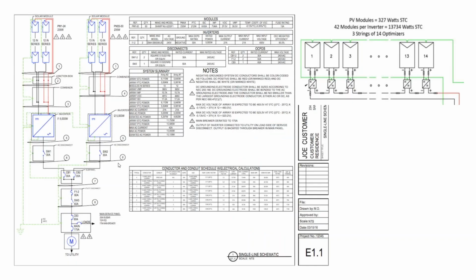So the question becomes: how do you determine the right setup? With Enphase microinverters, we know up to 16 per branch circuit. Microinverters are very flexible—if you just wanted a one-panel solar array, a microinverter would work just fine. String inverters, on the other hand, require you to know how many modules you can wire into a circuit so you don't overload the string inverter, which relates to the temperature coefficients we discussed earlier.